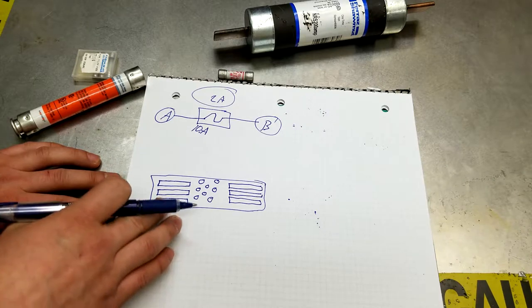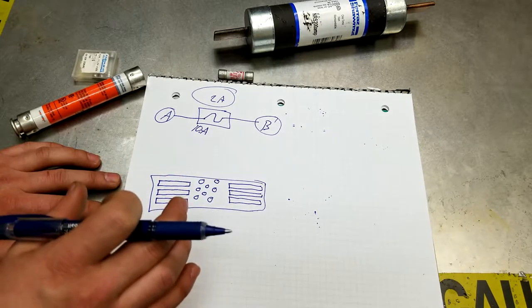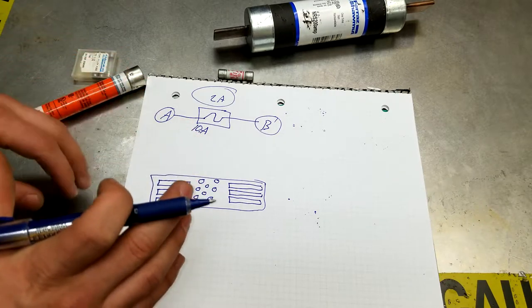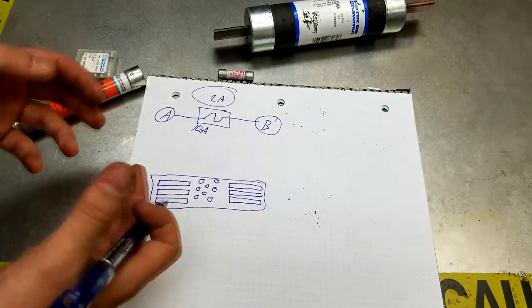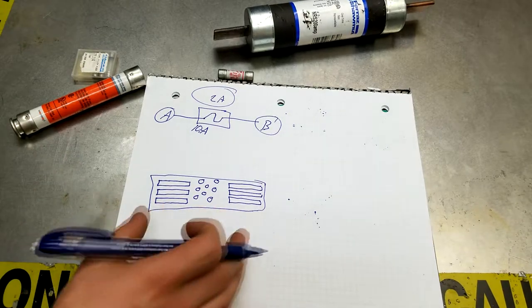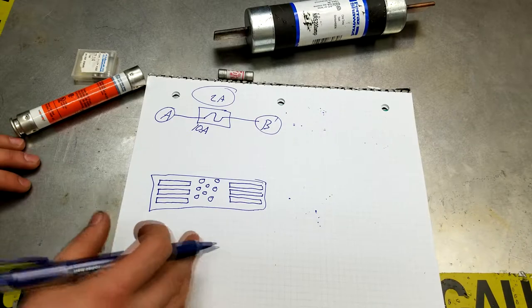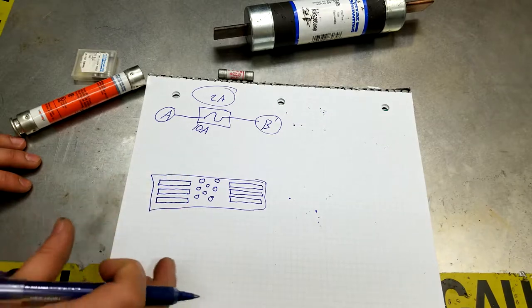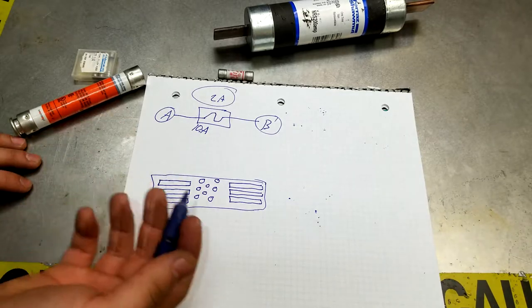Now your fast action would be actually rated precisely to the current that your fuse is rated for. But I really don't know how it works, because dual element fuses, they never blow at the rated current. I think it's kind of sad. Because let's say this is a 100 amp fuse. And it will never blow at the 100 amps. It will get really hot, but it would never blow. It's always a little bit higher, it's rated like a little bit higher.